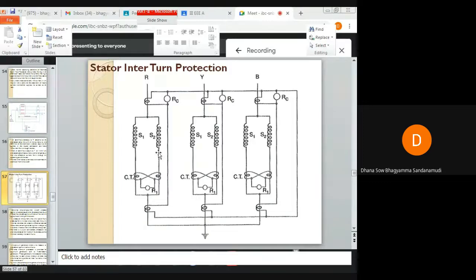So why are double windings used in hydroelectric generators? The reason is that they have to carry very heavy currents. Whenever the windings of the generator have to carry very high currents, in such a case we will go for double winding, triple winding, and so on. So we need to provide interturn protection. What I am showing here is the schematic arrangement of the circulating current and interturn protection for the three-phase double wound generator.